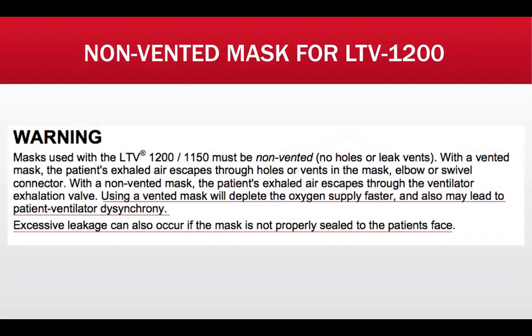The LTV-1200 by CareFusion states in its warning that the mask employed should be a non-vented mask, meaning there should be no holes present in the mask. If you use a vented mask, it will deplete the oxygen supply faster and may lead to patient-ventilator dyssynchrony, a fancy term for patient-ventilator bucking. Excessive leakage can also occur if the mask is not properly sealed; troubleshoot by adjusting the Velcro straps and confirming there are no air leaks around the mask.